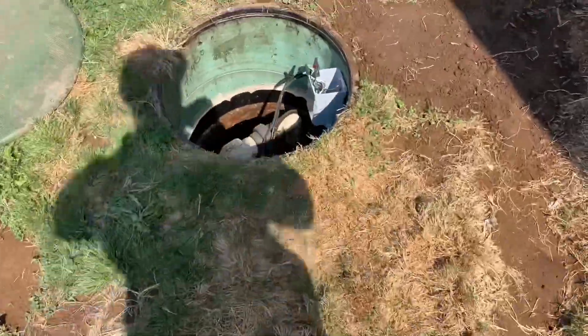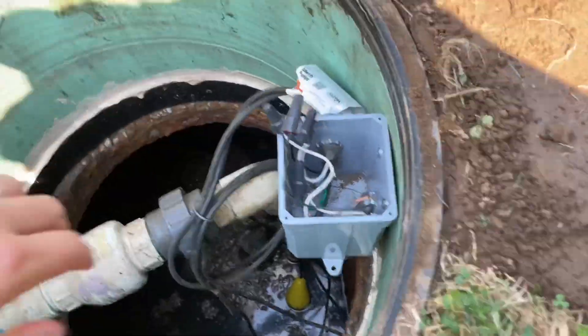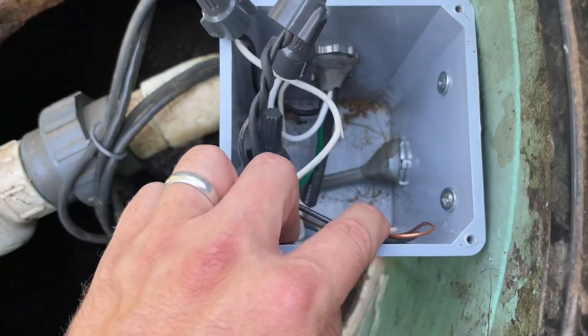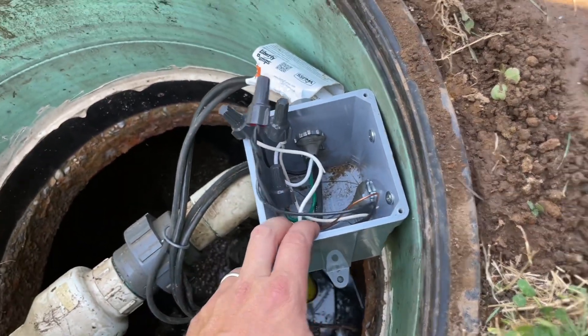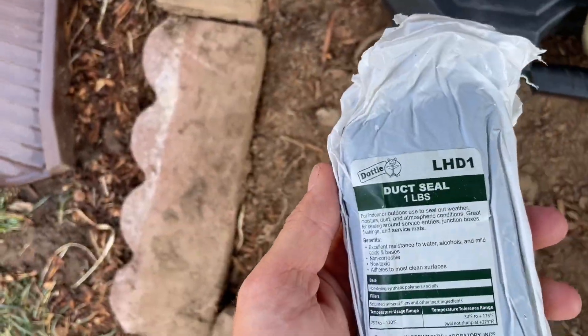One thing I forgot to mention: you've got to seal up all the conduit with duct seal, right there. It prevents moisture from getting in. I just used some of this stuff by Dottie.